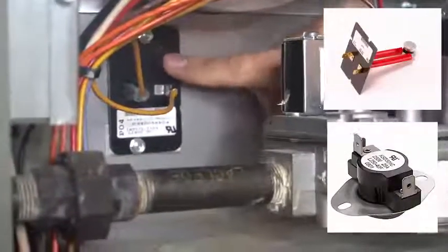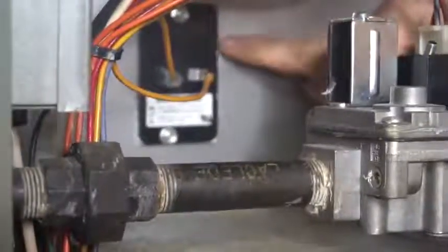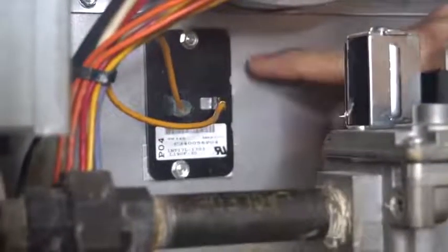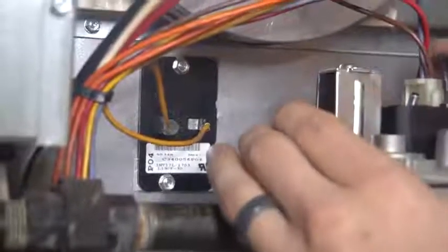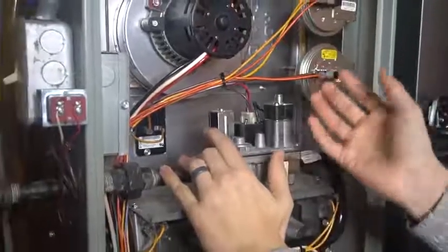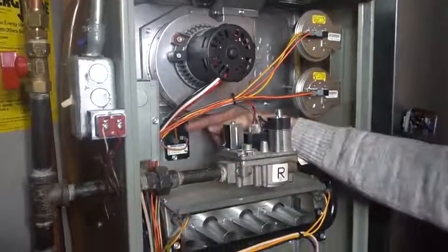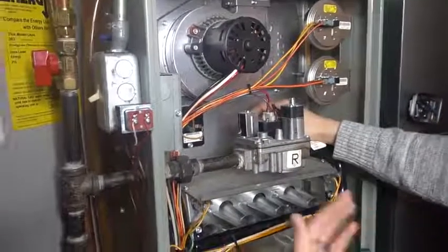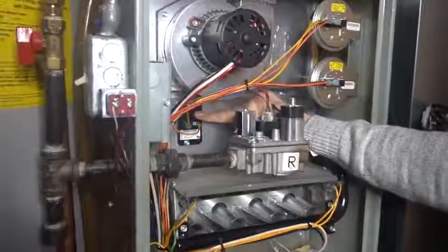And what this thing does is basically makes sure that the furnace inside is not overheating. So for example, if you have a very dirty filter, if you haven't changed your furnace filter in a long time, that means your furnace will not have enough airflow. So the heat that's building up in the heat exchanger will keep getting higher and higher because the airflow is not absorbing that heat and bringing it to your house. As that heat builds up in your furnace, this switch here will trip and turn off the burners and leave the fan on to cool off the furnace. So this is basically a switch that prevents the furnace from getting too hot.